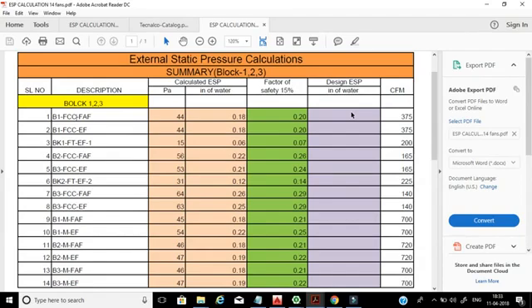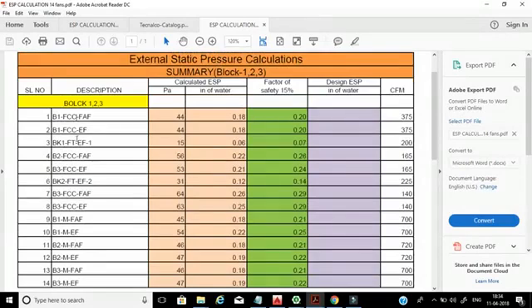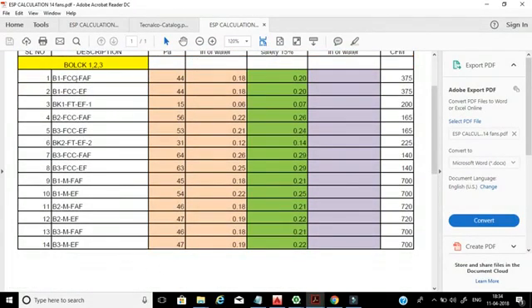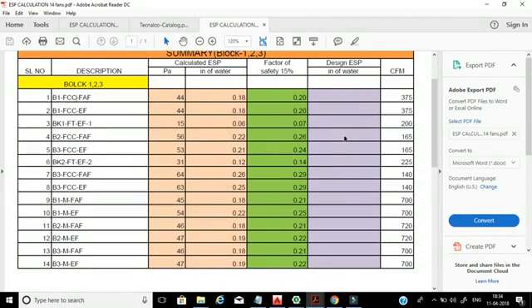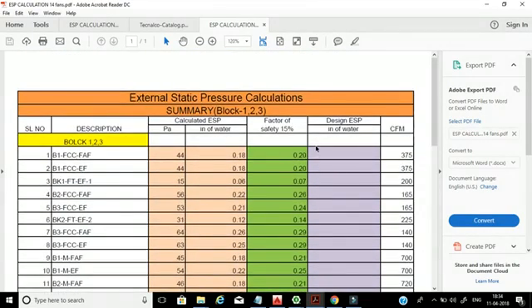If the design ESP is lower than our calculated value, the selected fan or FCU will not push the air to the last point of the HVAC system, and the supply air velocity or CFM will be very low — that is a problem for the cooling system. However, if the design ESP is 0.25 and our calculated value is 0.20, then we are on the safe side. We are under control. All the fans or FCUs can be mentioned in this summary sheet along with their design ESP from the equipment schedule drawing.